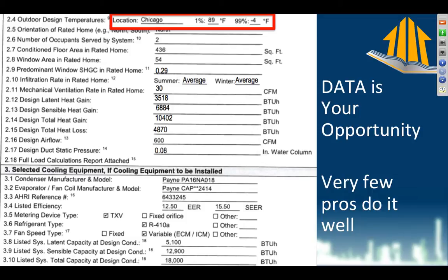Now someone will say, well, in Chicago last year it got down to -20, so I should put -20 in that box, right? Absolutely not. Last year when it hit -20, I emailed all my previous clients: 'Just so you know, today it's -20.' That means if your system was installed and designed properly, even at the 100% coldest day, even if the professional had put -20 in that 99% field, your furnace should be running 24 hours a day, nonstop. Mostly what I heard back was, 'Oh yeah, it runs for about half an hour and then turns off for about half an hour.' That means your furnace is over twice as big as it needs to be for that house.